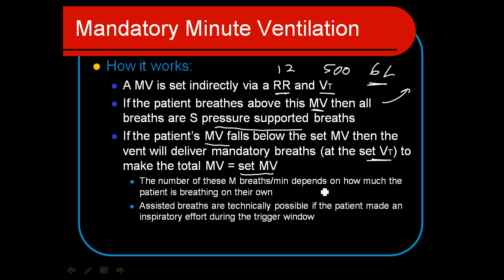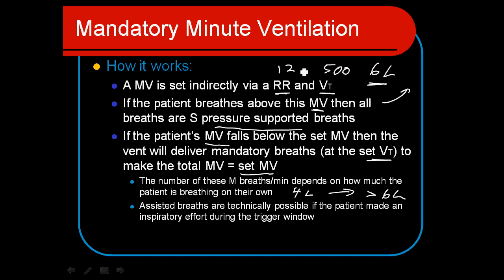The number of mandatory breaths depends on how much the patient is breathing on their own. If they're doing, say, four liters per minute on their own, the ventilator will kick in and give enough breaths to bump them over that six-liter goal. So if they go totally apneic, it would fall back to the set rate of 12 at 500 mL to deliver the full six liters.